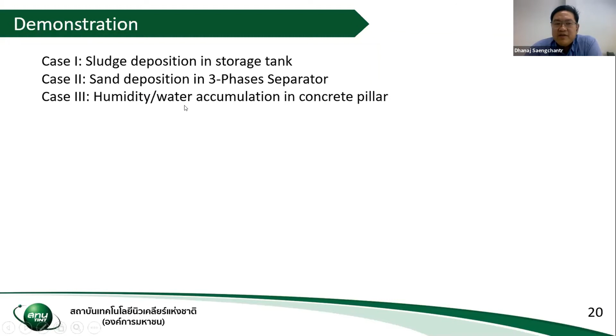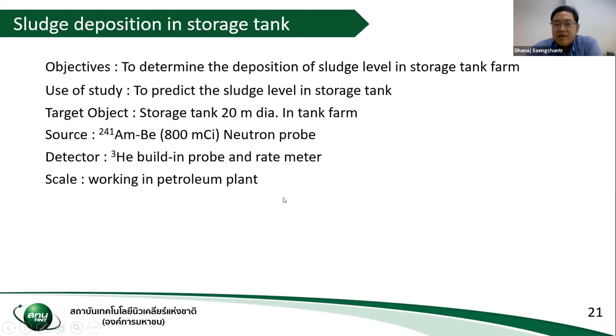First, we talk about the sludge deposition in the storage tank. The objective is to determine the sludge deposition level in the storage tank farm, and the study is used to predict the sludge level in the storage tank. The tank is about 20 meters in diameter, and we use an americium-beryllium neutron source and a helium-3 detector. And we were in the petroleum tank farm branch. So this is the tank. The height is about 16 meters, and the measurement elevation interval is about 5 centimeters. It means that we move the probe 5 centimeters each step, scanning from the bottom to the top.